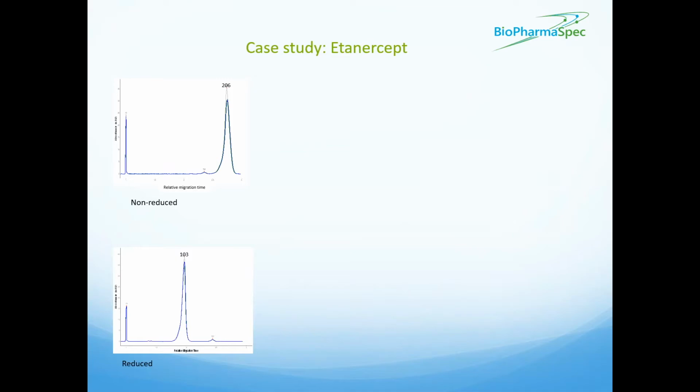and you will get an anomalously high run position. Nonetheless, we are using the Maurice system really as a batch-to-batch comparative tool and not as a mechanism of getting an accurate mass per se. So it's perfectly fine that we see a higher mass than we would expect. In comparative terms, the 3 batches that have been run here are all showing the same thing, and that's the important thing. They're all handling in the same way.